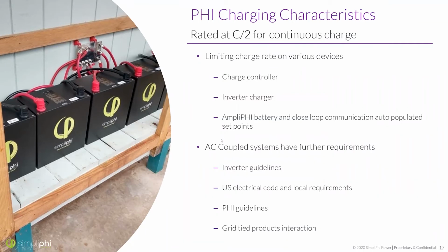All right, back to it. So again, charging, you want to limit your charger. Charge controllers, just set that limit. Super easy. Calculate how many batteries you have. Look at your charge limit. It's in all of our manuals, all of our spec sheets, all of our integration guides, has that value written out in really plain, hey, it's this value. And if it's a specific inverter that we have an integration guide for, it'll tell you exactly what they're going to ask the value to be in, whether it's kilowatts, whether it's amps, whether it's a percentage.